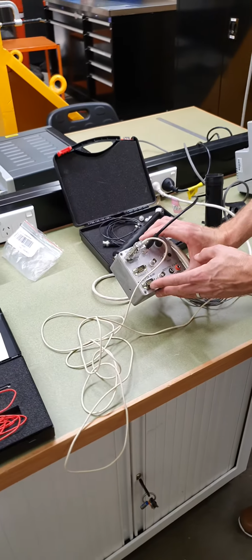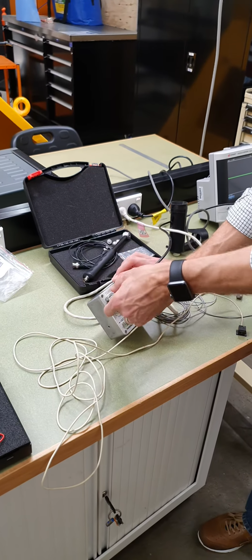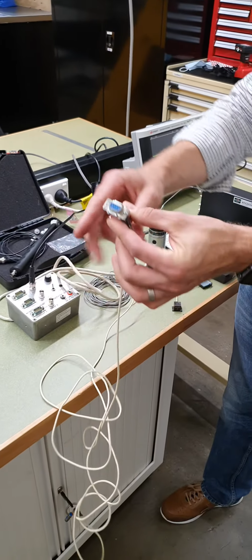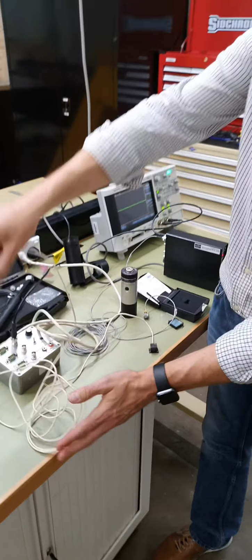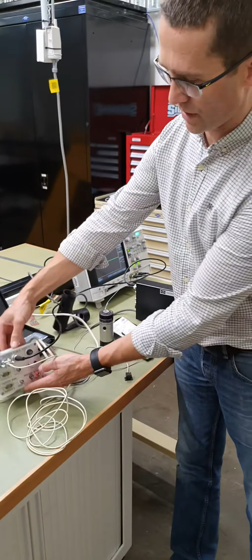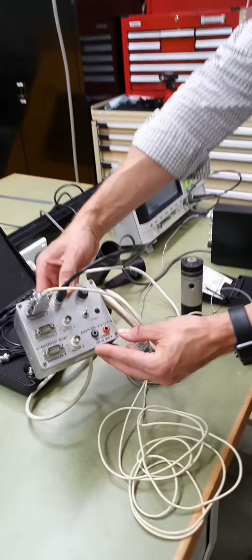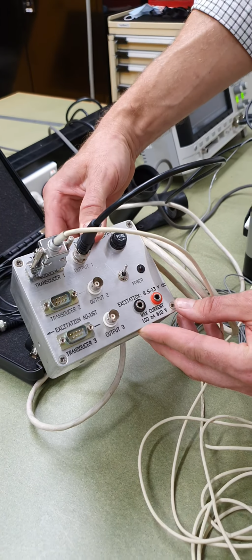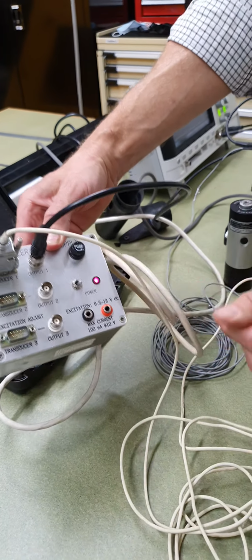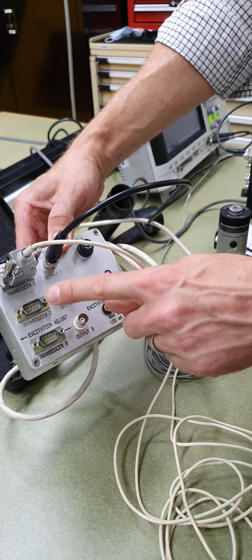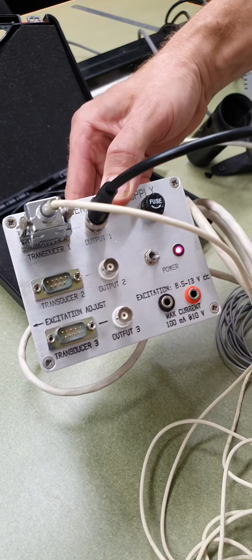So I've got a separate type of signal conditioning system for these types of transducers that's connected. These are all connected with a D-sub 9-pin connector. These are fitted here. This is a 3-channel device, which is an internal protocol that we have. And this is also mains powered. And again, you've got inputs for the transducer and outputs to the measurement system.